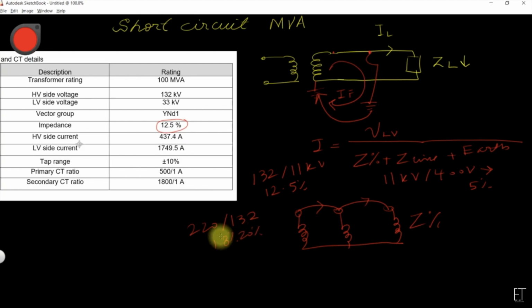So if the voltages are increasing, the fault levels are also increasing, and we want to control the fault current. We can control the fault current by increasing the impedance of the coil itself, because this is the limiting factor in case of a fault on the terminal of the transformer. We design transformers for the worst possible fault condition, normally a three-phase short circuit. So this is one case. Secondly, while doing the setting calculations, we have to make sure that in case of short circuit, our differential protection is able to pick up and trip in case of an in-zone fault.